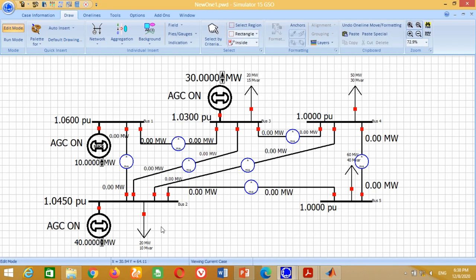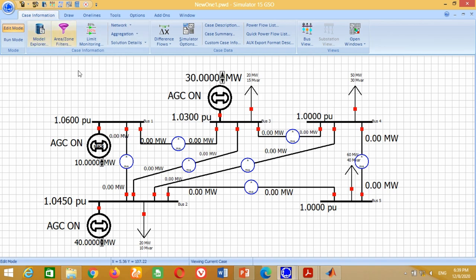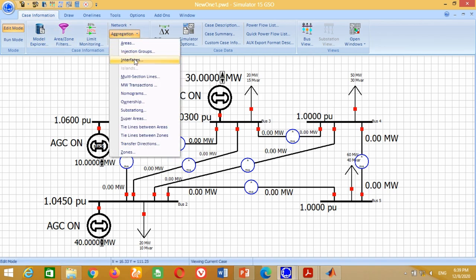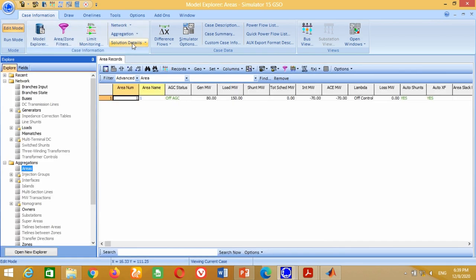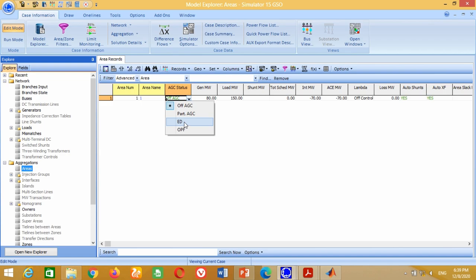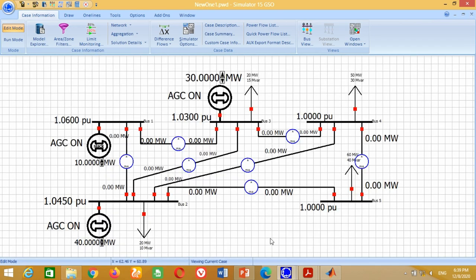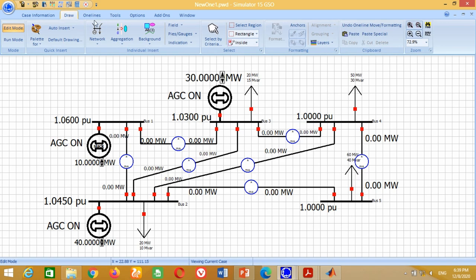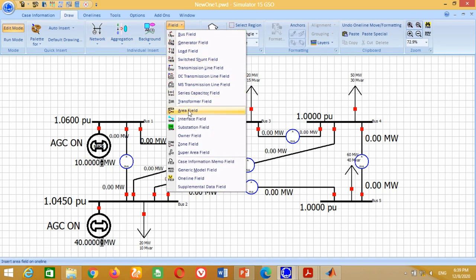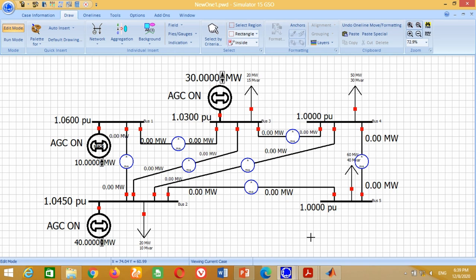Now we have to activate the economic load dispatch mode in order to perform the optimal dispatch of generators. For this purpose, go to Case Information, then Aggregation, click on Areas, and change the AGC mode from Off to Economic Dispatch mode. Now go to Field, click on Area Field and put it anywhere on the screen. Click on Hourly Cost and press OK to measure the total cost.